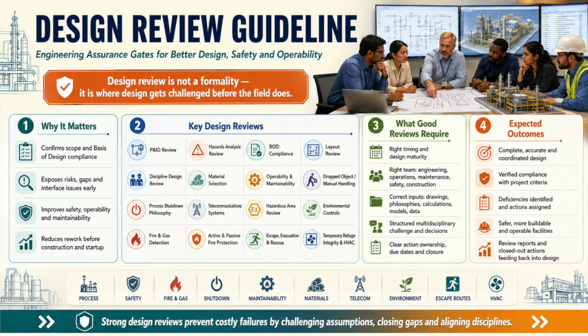The Hazardous Area Review checks that area classification drawings are accurate, complete, and consistent with process sources, ventilation, equipment locations, P&IDs, layouts, and electrical and instrumentation selections. Misalignment between hazardous area drawings and the physical design can produce incorrect equipment certification, unsafe installations, procurement changes, construction rework, and compliance failures. Environmental control reviews challenge gaseous emissions, liquid discharges, solid waste, noise, energy use, regulatory commitments, customer objectives, and environmental hazards.